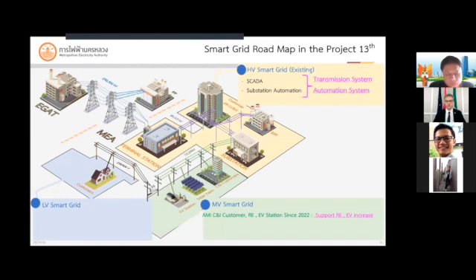AMI for commercial, industrial, or C&I customers, and RE EV stations will be installed from 2022 to support increasing RE and EV. AMI and OLTC, or on-load tap changer transformers, will be installed to support solar rooftops from 2022. A full DMS, or distribution management system, will be installed in 2024 to reduce the duration of feeder outage within 15 minutes.